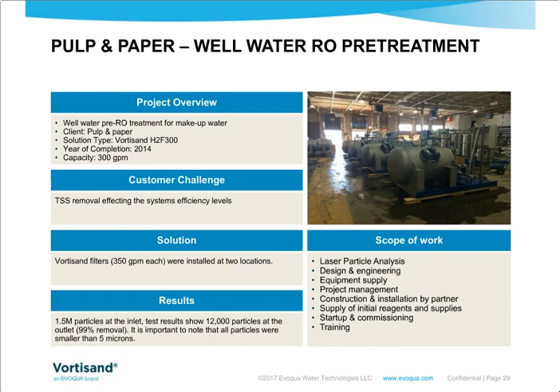And what we saw was about 1.5 million particles at the inlet, and then after a 99% removal, particles dropped to about 12,000 particles that were 5 microns or less. So, a drastic improvement for the pulp and paper mill for a pre-RO application.